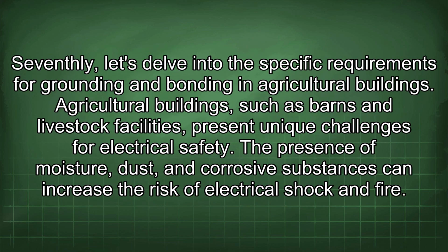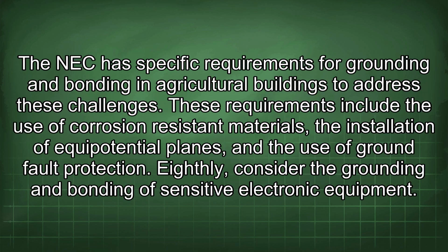Seventhly, let's delve into the specific requirements for grounding and bonding in agricultural buildings. Agricultural buildings, such as barns and livestock facilities, present unique challenges for electrical safety. The presence of moisture, dust, and corrosive substances can increase the risk of electrical shock and fire. The NEC has specific requirements for grounding and bonding in agricultural buildings to address these challenges. These requirements include the use of corrosion-resistant materials, the installation of equipotential planes, and the use of ground fault protection.